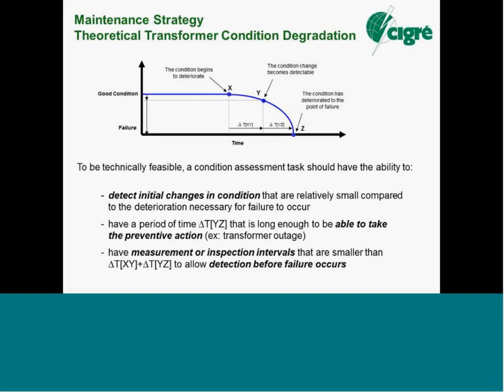And an interesting point with condition-based maintenance is that its trigger is a change in condition. You're not doing time-based maintenance, where you have a prescribed maintenance interval to do your repetitive routine maintenance. Instead, the actual condition of the transformer is the trigger for action.